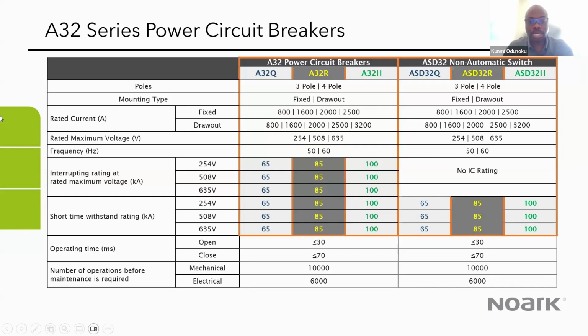When we say the operating time, we're referring to the time from when the breaker gets the trip command to when the contacts physically separate inside the breaker. So that's the operating time, and it's within 2 cycles. And of course, we have the number of operations as well, the mechanical and the electrical.